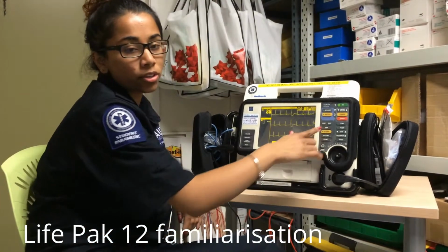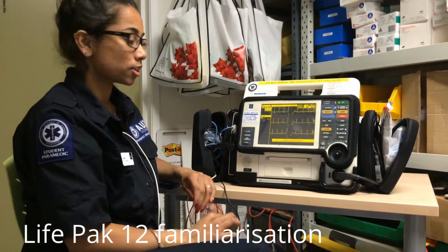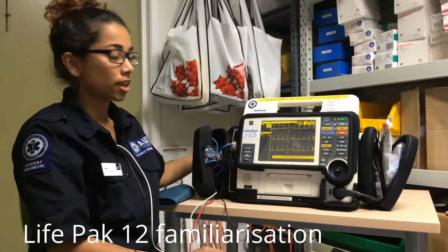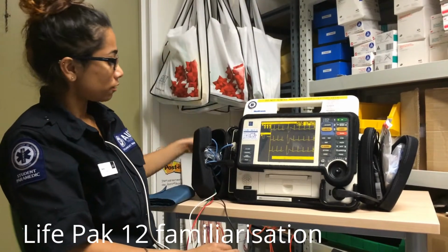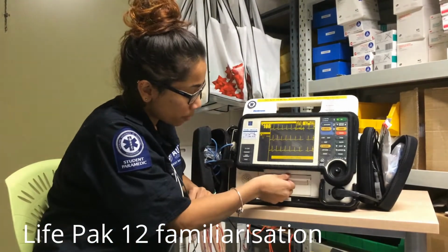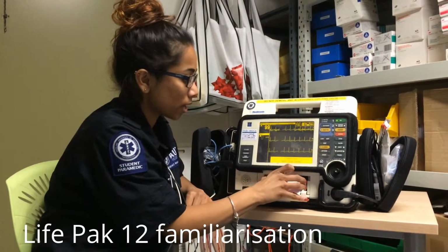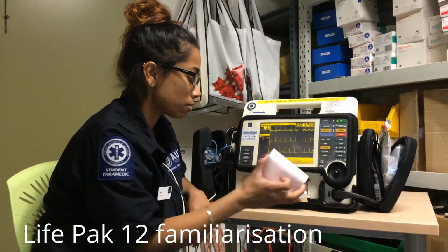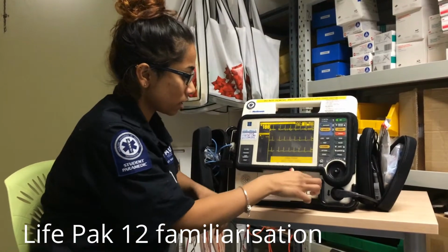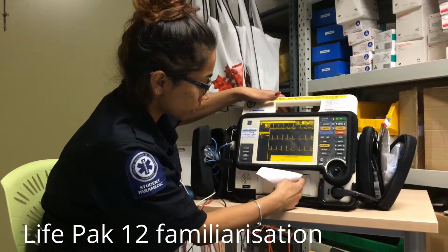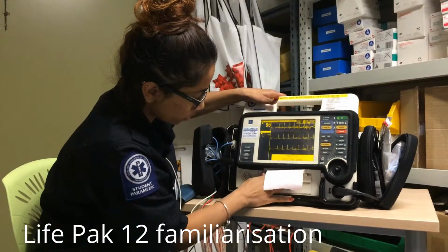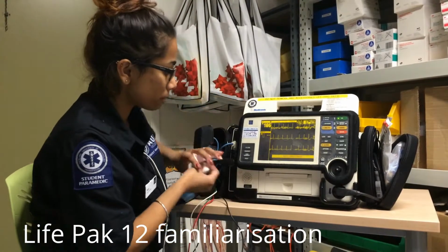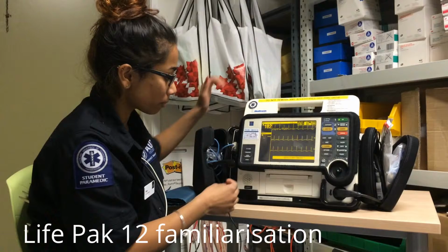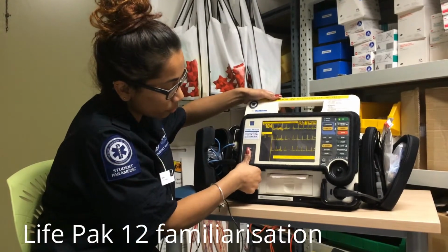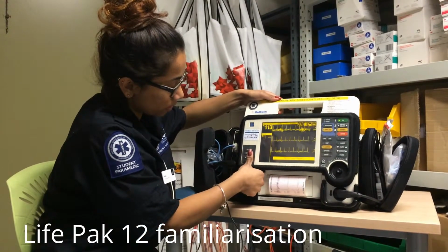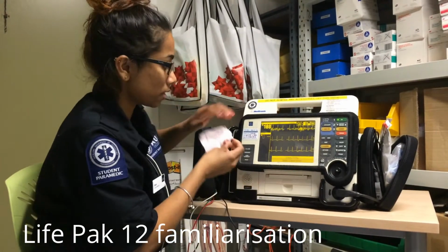So also to change the ECG paper, there should be a spare roll located at the back of the LifePak, like so, and if you want to change it, all you need to do is pull out the paper like so, pull out your empty roll, put in a new roll, and you want to then close the port like so, and you want to check that it is in properly, so you want to click print, and it will print out some paper, and then you know that it is actually in there.